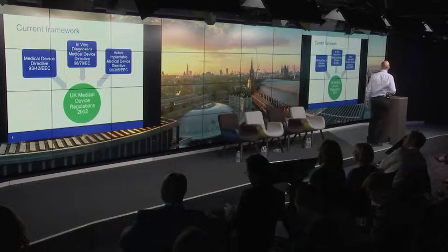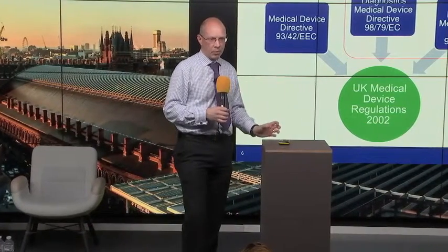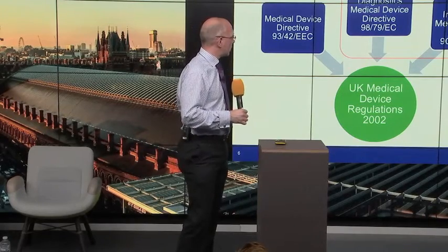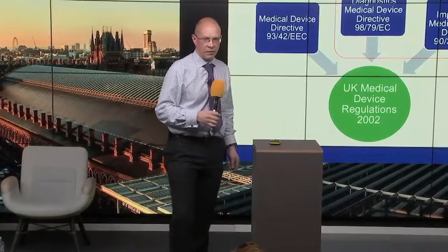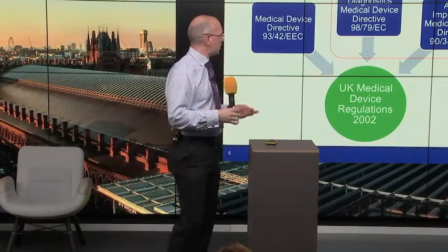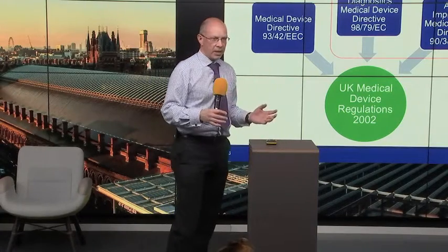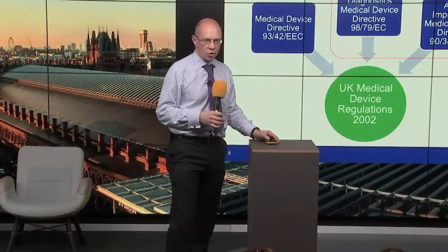So the current framework is there are 3 European directives: a General Medical Device Directive, an In Vitro Diagnostic Medical Device Directive, so that's based on samples taken from patients and analysed in a lab, and the Active Implantables Medical Device Directive, which looks at, well, implantable devices that are powered, so pacemakers and the like. And then they're implemented into UK law as the Medical Device Regulations of 2002.